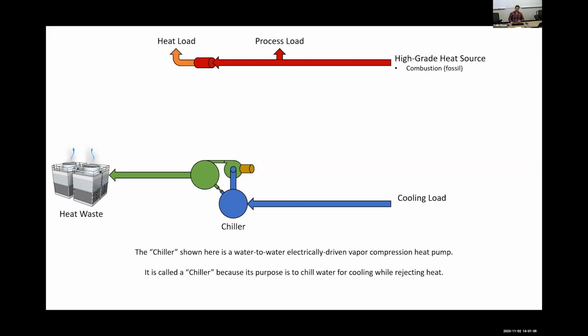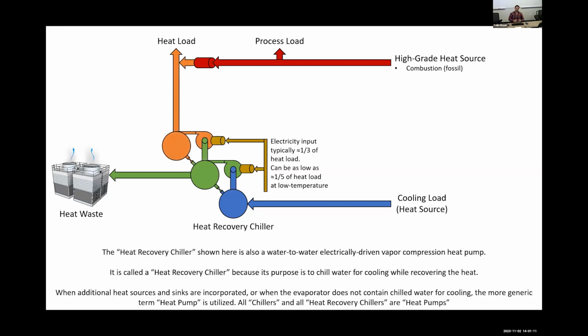So it's called a chiller. It's a heat pump, but we call it a chiller because its main purpose is to chill water. And then we can change that chiller into a heat recovery chiller. This is also a heat pump, but the heat recovery chiller is called such because some of the heat from the chilled water can be recovered for beneficial use in the heating system.